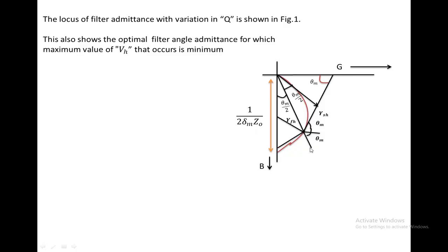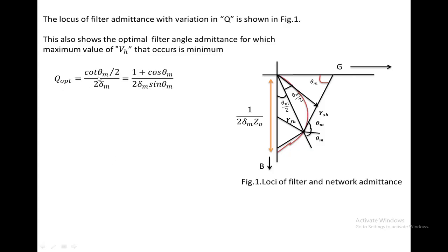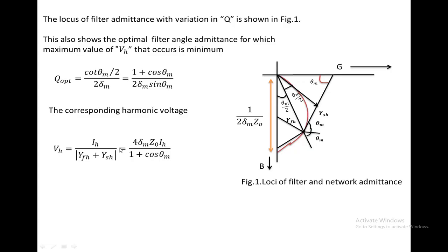Extending this line and drawing a parallel to the x-axis, the angle theta_M appears on both sides. From this locus of admittance by varying Q, we can find the optimal Q value, which equals cot(theta_M/2) divided by 2·delta_M. This can also be written as (1 + cos(theta_M)) divided by (2·delta_M·sin(theta_M)). The harmonic voltage at the converter bus is then VH = IH / (YFH + YSH) = 4·delta_M·Z0·IH / (1 + cos(theta_M)).